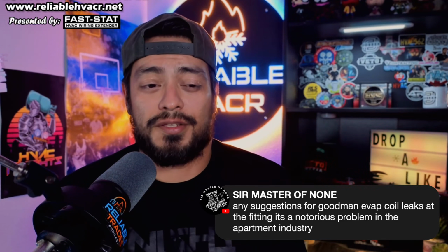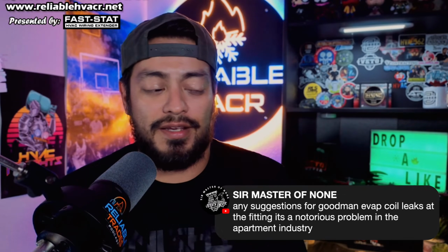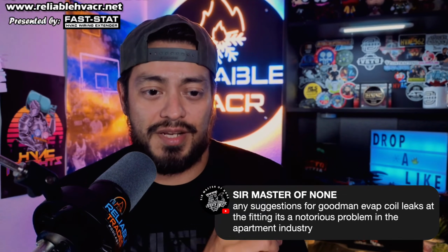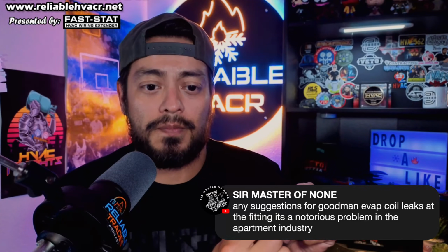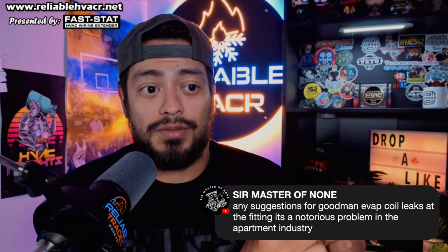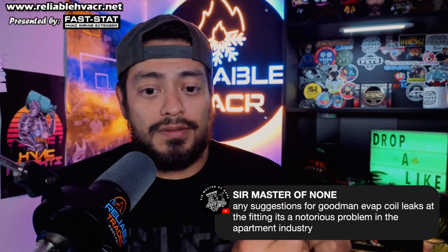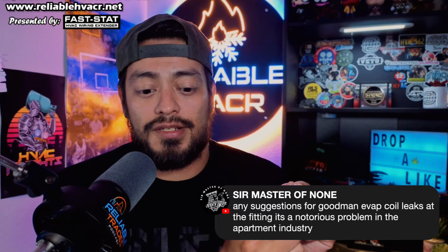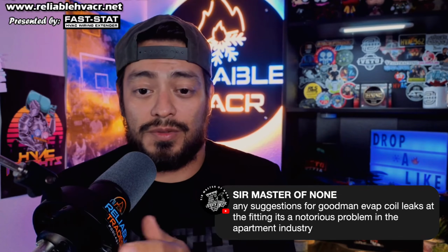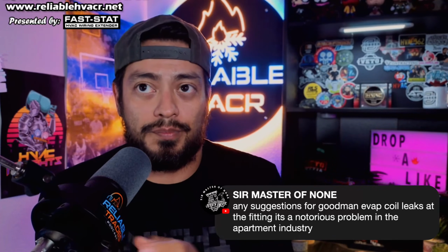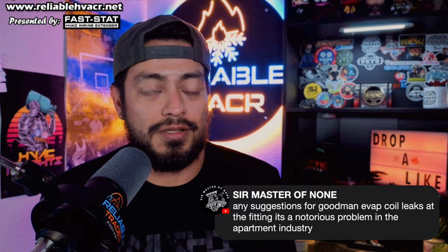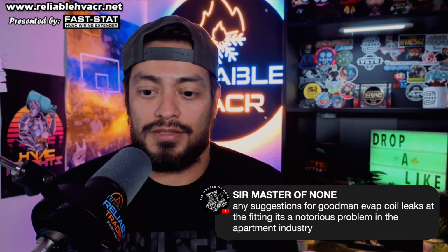For me, it's like the rooftop units. They leak, I think, at the same point. If it's copper to aluminum, that's where they always leak on these microchannels on RTUs. The only thing you can do, depending—I had one that was cracked on the aluminum side for sure, and I'm not sure if it was leaking at the fitting too.